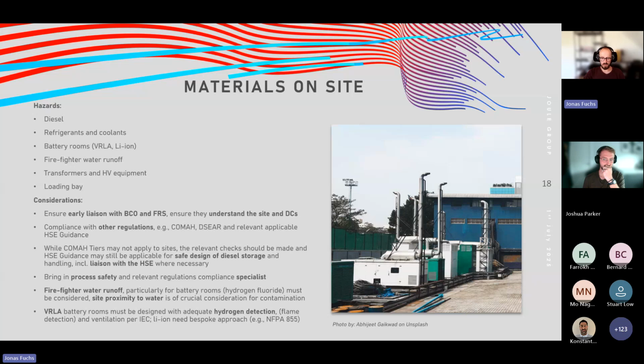Firefighter water runoff has not been particularly well designed in the past, and existing sites might not have the provisions. With current technology, for example lithium ion, chemical reactions can produce toxic runoff that needs to be processed accordingly, specifically for sites close to water sources. It's important that firefighter water runoff is catered for through on-site capture. For VRLA battery rooms, the technology produces hydrogen when charged, so hydrogen detection, ventilation, and other safety systems, such as intrinsically safe electrical equipment, need to be put in place. It's certainly one of the more complicated buildings around to design for.